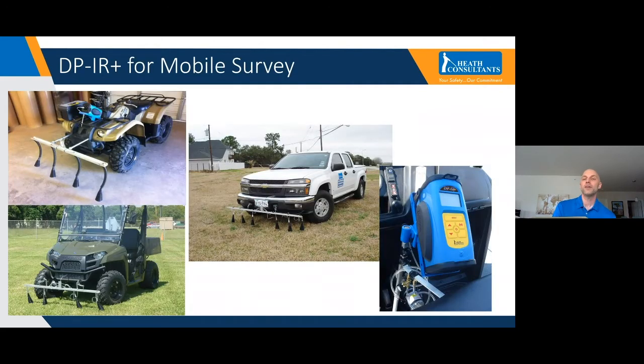On the mobile survey side of it, Heath really has our bases covered when it comes to doing mobile surveys. There are a lot of options out there. You've got your advanced mobile surveys that are capable of going down to 1 part per billion. You've got the Heath optical methane detector, the OMD. But what I'm talking about here is using the DPIR for a mobile survey. When you're doing that, the instrument itself is integrated with an external pump and drop cones. Each of these instruments has a Heath mobile kit, so if you do use the DPIR for mobile survey, we do recommend using the Heath mobile kit on it.